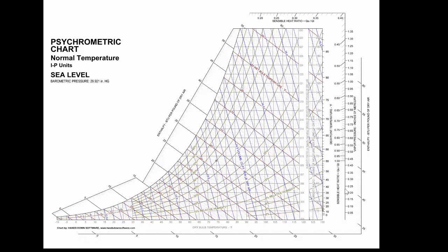We can demonstrate this process on the psychrometric chart, and we can determine the state properties, similar to the procedure we described in the earlier examples. The outside air was given at 95 degrees Fahrenheit and 20% relative humidity, as you can see. So we can cross those two lines here to determine the state point for the outside air, or incoming air, through the pad.